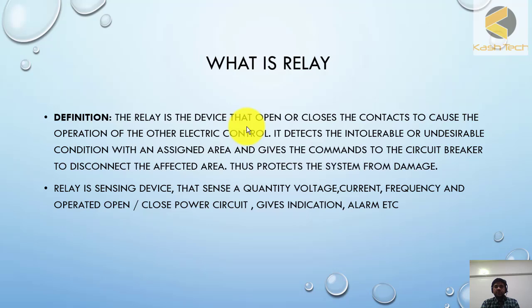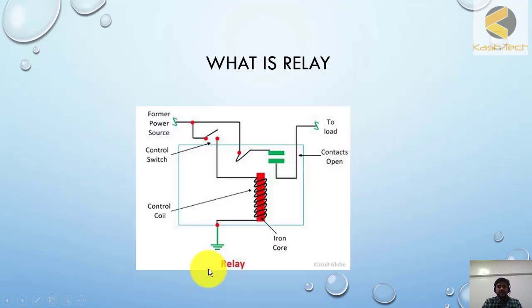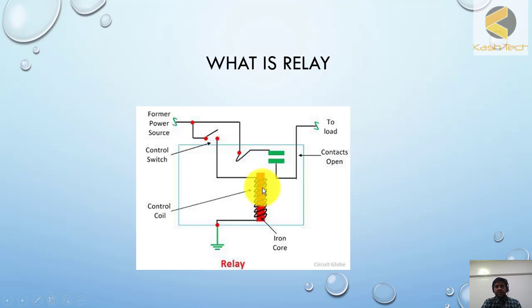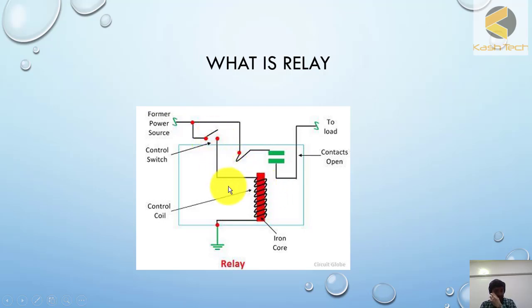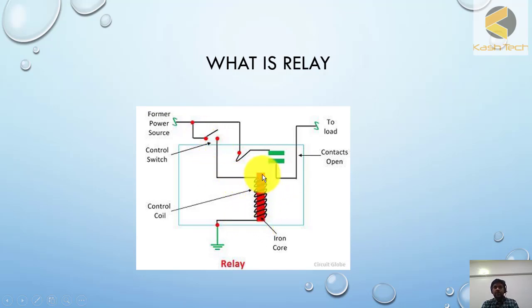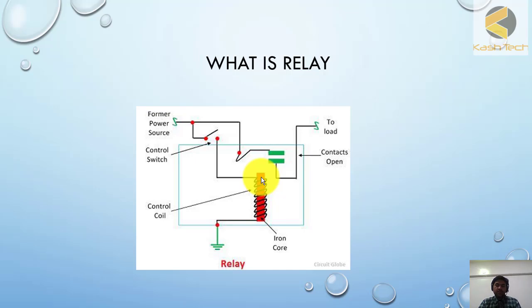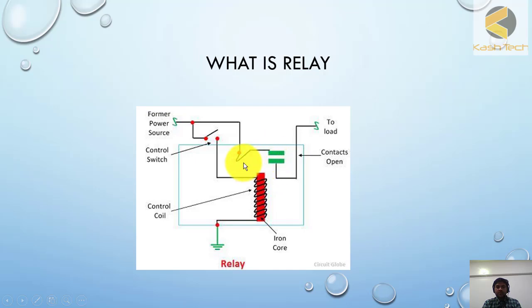Let's see an example here. This is a control relay which is controlling the circuit itself. If somebody pushes the button, current will flow through this coil, and this coil has an iron core - it will attract this contact. With the magnetic attraction, this contact will close and the load will be connected. So this is an example of a relay used in a control circuit. It is sensing current and allowing power to connect to the load.